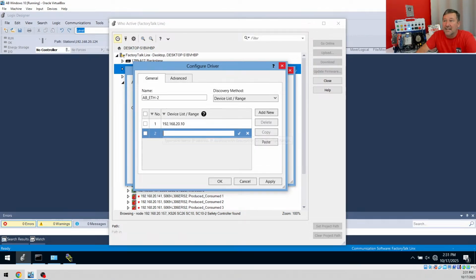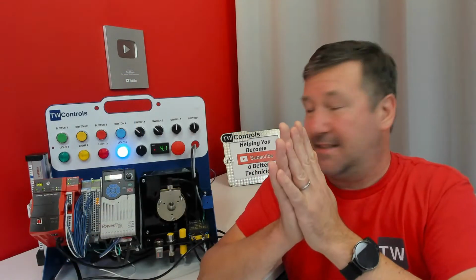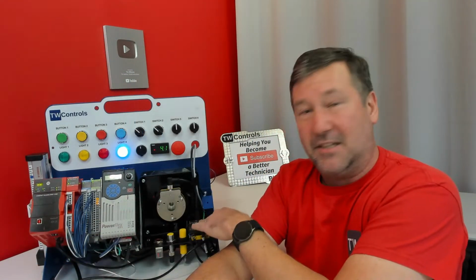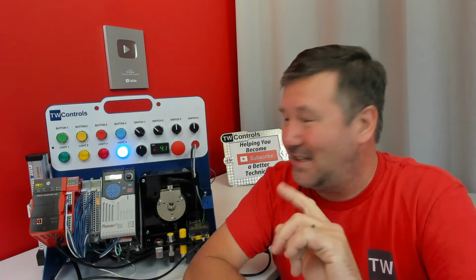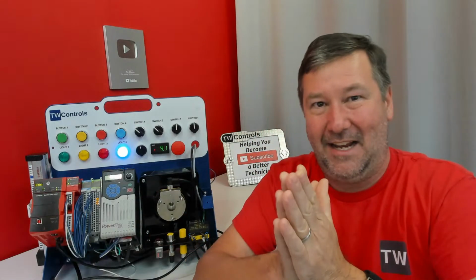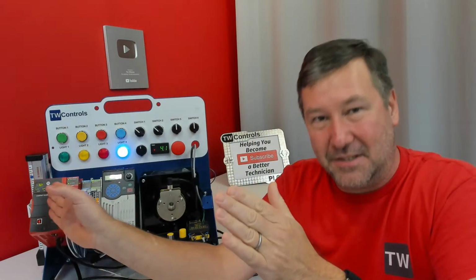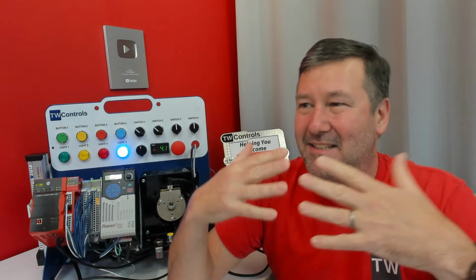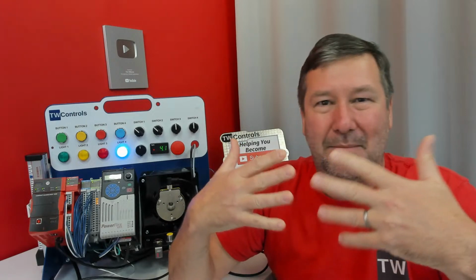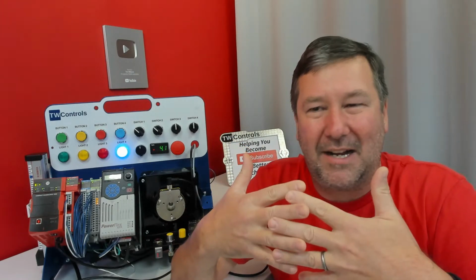192.168.20.10. In this case, it's not going to look at this PowerFlex. It's only, arguably, I know it's not exactly it, but just like we use the ping to direct a packet to exactly there, now these packets are only going to go to this one spot. So it's going to get us out of any type of things that may be blocking broadcast.